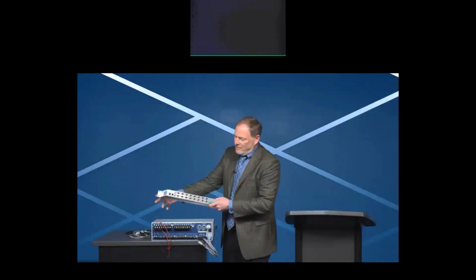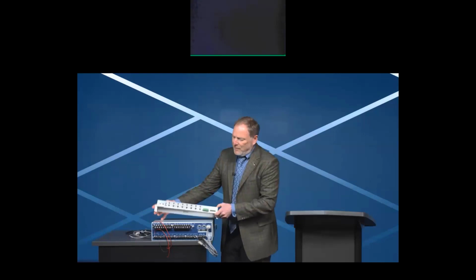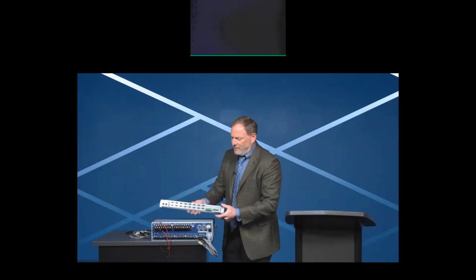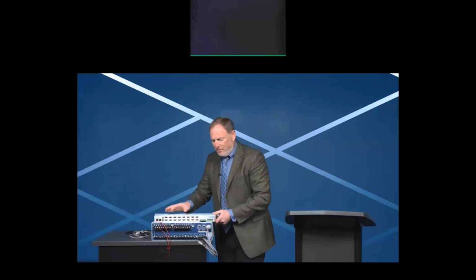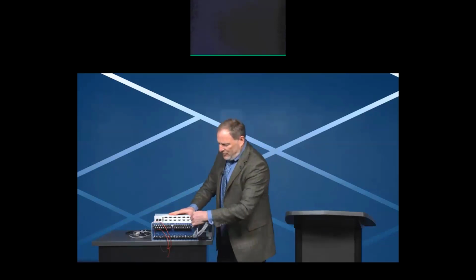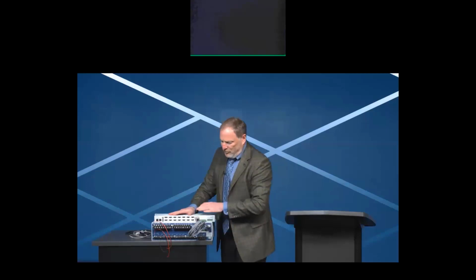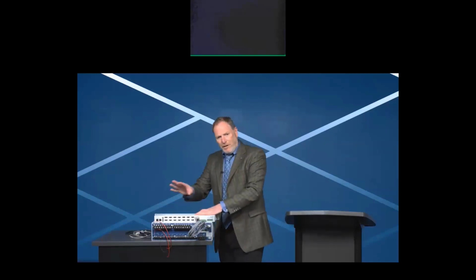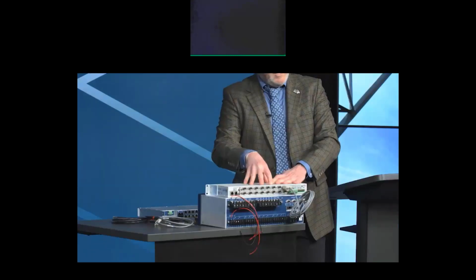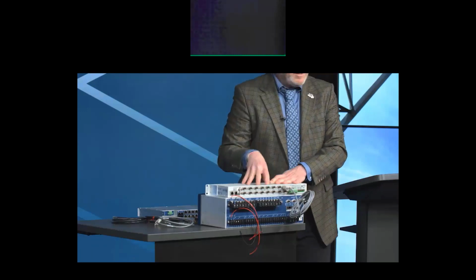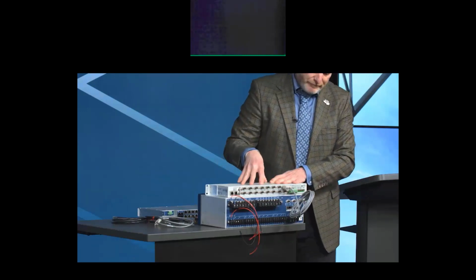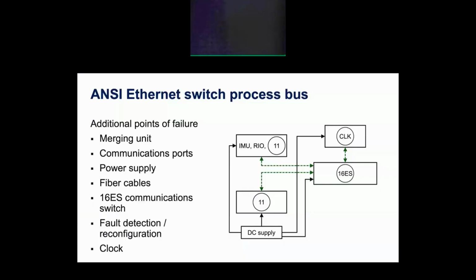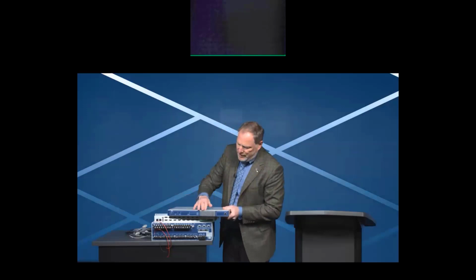The ANSI number for a communications switch is 16, and a 16SS is a serial switch. So here's the SEL version of a 16SS serial switch where we use RS-232 connections so that we can communicate from the merging unit or the relay to the switch, and then from the switch to several other devices. And in this example, this 16SS serial switch is built the same way as our relays, and it has an MTBF of 620 years. And here we see an ANSI 16ES, which is an Ethernet switch.